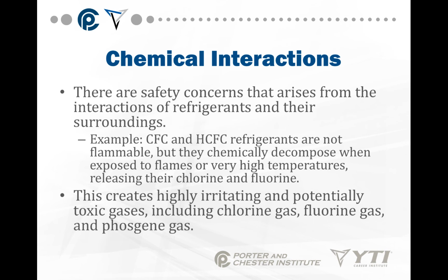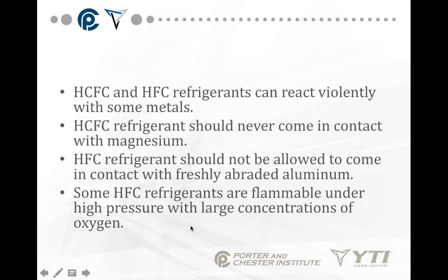For example, CFC and HCFC refrigerants are not flammable, but they chemically decompose when exposed to flames or very high temperatures, and they release chlorine and fluorine. Okay, this creates a highly irritating and potentially toxic gas, including chlorine gas, fluorine gas, and phosgene gas. So with CFCs and HCFCs, you only want to braze line sets that are empty, first of all, because of pressure regulations. You don't want them to blow apart when you heat them up just from pressure. But you also don't want to burn that refrigerant because the phosgene gas can actually kill you.